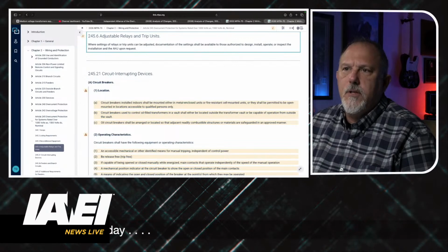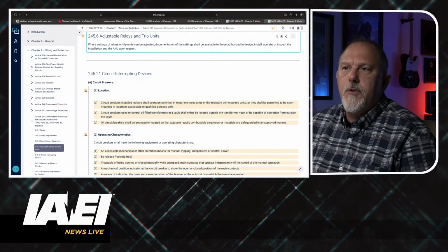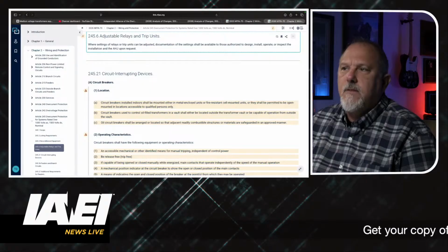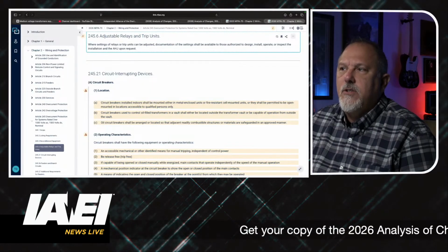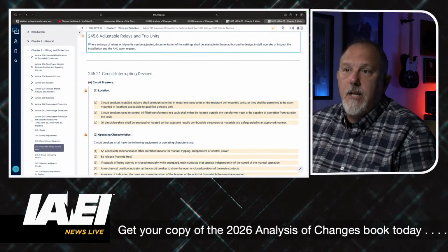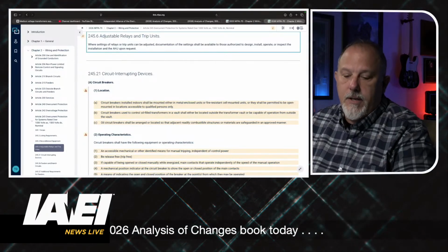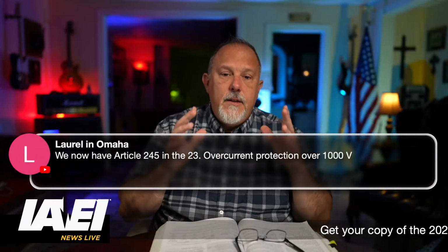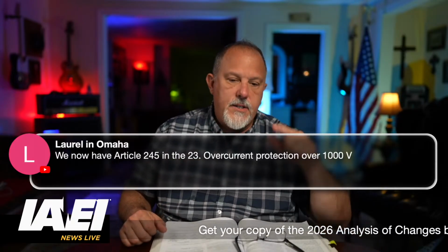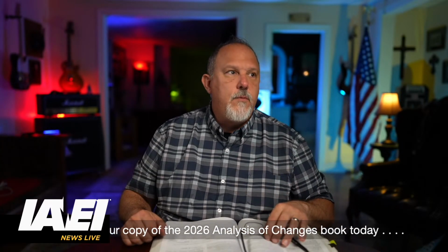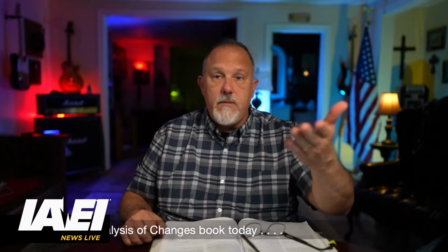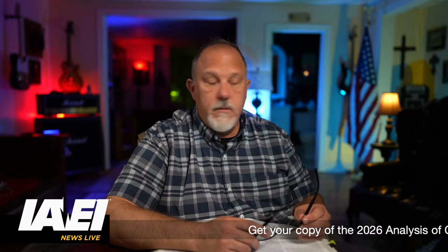What does adjustable relays and trip units say? Where settings of relays or trip units can be adjusted, documentation of the settings shall be available to those authorized to design, install, operate, or inspect the installation and the AHJ upon request. So the key thing there is that we have some guidance, but the point that Dawn made and Andrew made and Laurel's making, hey, I don't have any standard ampere ratings in there.